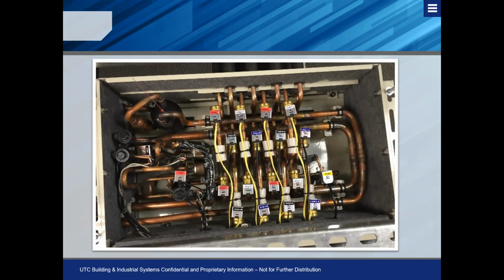Okay. But when we break this box down, we stated that there are three main components. The gas liquid separator, which of course is pretty straightforward. It's going to separate hot gas and liquid depending on whether we have simultaneous mode or whether we're running all heat or all cool. We have our brazed plate heat exchanger, which helps subcool that liquid refrigerant so we can make great distances with this box. And then finally, we have our individual solenoid valves, hot gas, liquid, and suction solenoids, depending on what the indoor units are doing.